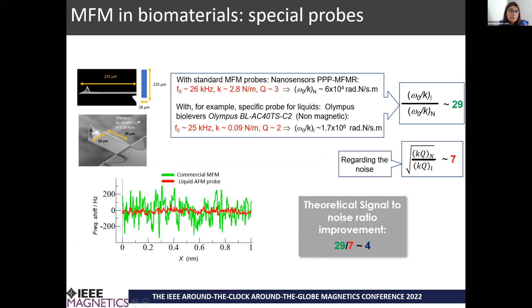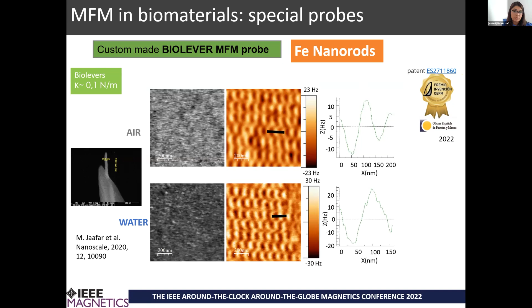Here we have a reference sample and we measure them with a nanorod, an iron nanorod of nearly 700 nanometers and 50 nanometers in diameter, to measure in air and in liquid. It's worth noticing that the quality of the MFM images acquired in liquid media is now very close to those acquired at ambient conditions. So we have an improvement in the signal-to-noise ratio by nearly a factor of 4 for these probes, in good agreement with our previous estimation of MFM noise.